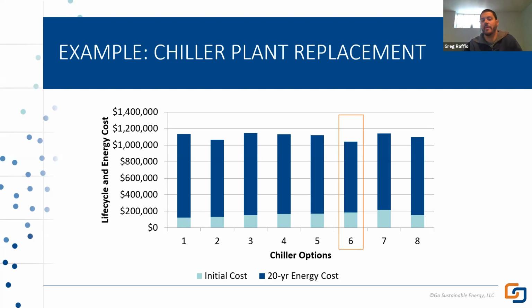They ended up going with option number 6. The light blue on the bottom of the graph was the initial cost of the chiller, and the dark blue was the lifetime ownership and energy cost—slightly out of whack with each other in terms of overall impact over 20 years. They could have gone with the most expensive chiller, about a $32,000 cost add, which on paper had a higher rated efficiency, higher IPLV, more bells and whistles.